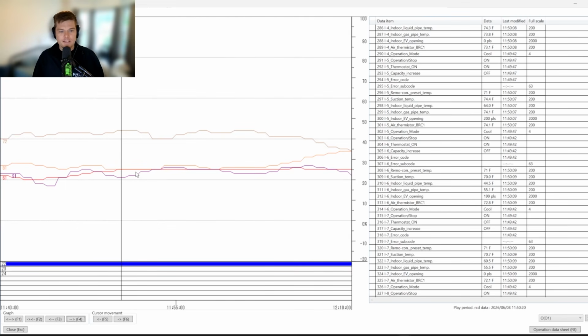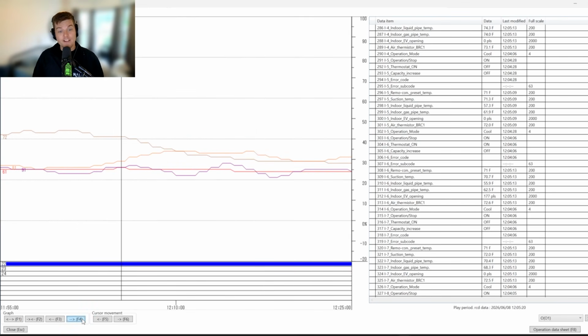So this isn't a particular issue, because if it continued, then yes. But you can see the wild fluctuations that we have here in those temperatures, right? This is changes in saturation, pressure, and temperature. The target's constantly changing. This is what you'll see with VRF turned on in a lot of systems. It's not just a matter of, okay, where's the liquid coming from? Maybe it's overcharged, and this system actually isn't overcharged. It actually might be a little bit undercharged. But you'll notice that when you move the goalpost on VRF systems, you can't just snap judge quick and say, yes, that's exactly what it is.